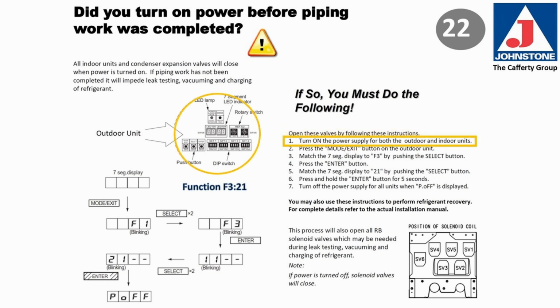Turn on the power supply to both the outdoor unit and the indoor units. Press the mode exit button on the outdoor unit. Look at the 7-segment display. Change that display until it displays F3 by using the select button. Press the enter button. Change the display to 21 by using the select button. Press and hold the enter button for 5 seconds. The display will now show POFF, or power off. You may turn off the power to all of the units and those valves will remain open.